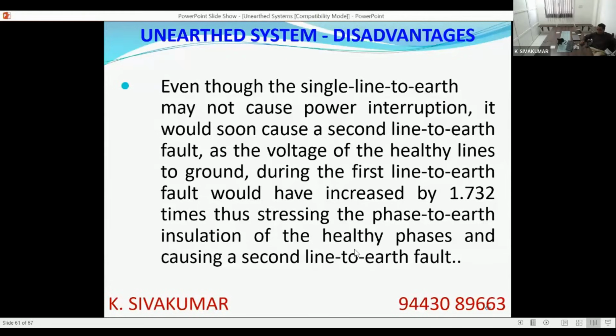Then the second phase and the third phase to earth voltage has increased, and its insulation will be stressed. So sooner than later a second line also will get grounded. There have been instances of an immediate second fault in the system. The voltage of the healthy line to ground during the first line to ground fault will have increased by root 3 times. Thus the phase to earth insulation of the healthy phases is stressed, so sooner than later there will be a second earth fault.